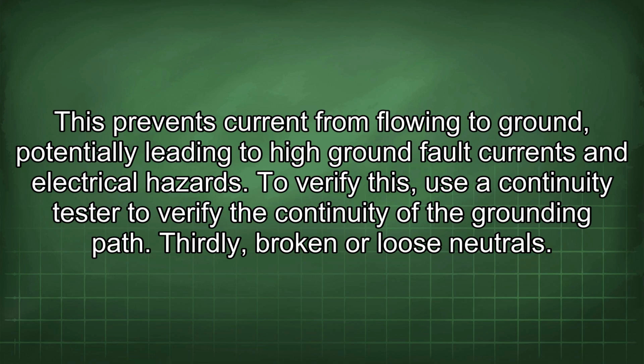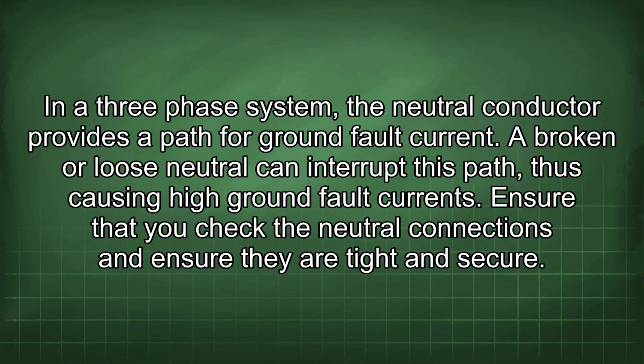Thirdly, broken or loose neutrals. In a 3-phase system, the neutral conductor provides a path for ground fault current. A broken or loose neutral can interrupt this path, thus causing high ground fault currents. Ensure that you check the neutral connections and ensure they are tight and secure.